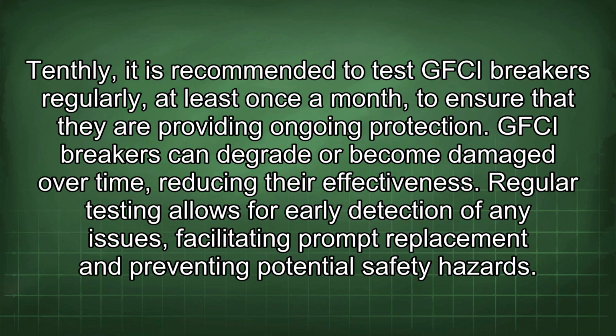Tenthly, it is recommended to test GFCI breakers regularly, at least once a month, to ensure that they are providing ongoing protection. GFCI breakers can degrade or become damaged over time, reducing their effectiveness. Regular testing allows for early detection of any issues, facilitating prompt replacement and preventing potential safety hazards.